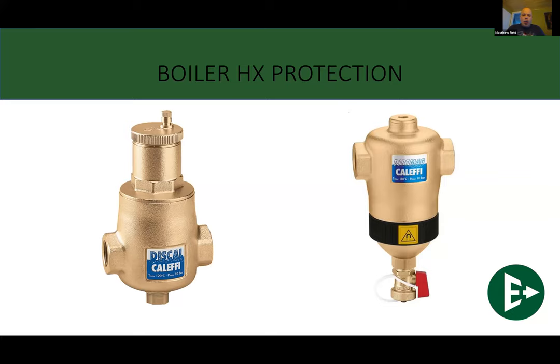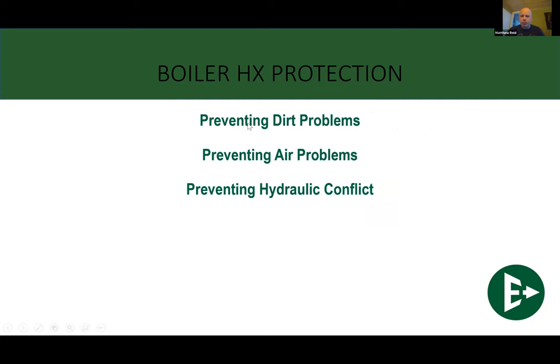Okay, so we're going to get now into our boiler heat exchanger protection. So we've put in this brand new boiler. Your pumps cost a couple hundred bucks, your other pieces in there cost a couple hundred, but your boiler's costing you thousands. That's the piece to protect. Bar none, absolutely 100% of the time. Look after that piece. So this is how we do it. We prevent dirt problems, but first and foremost, we've got to prevent air problems. Air on its own will lead to dirt problems.